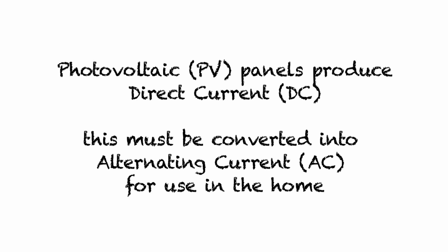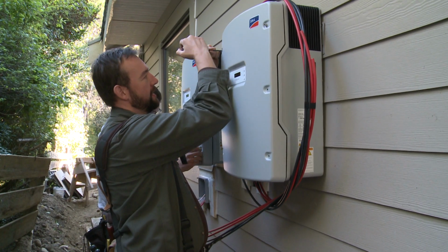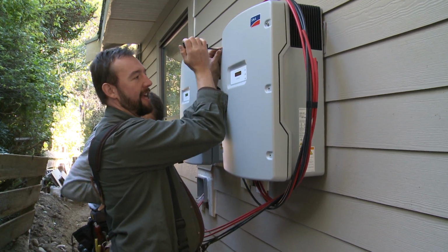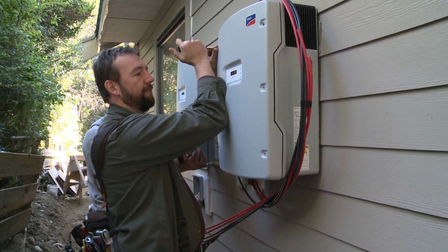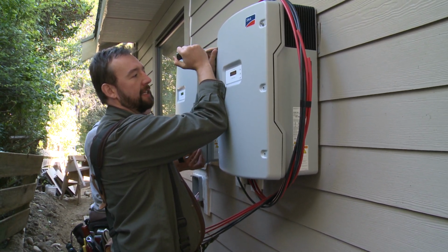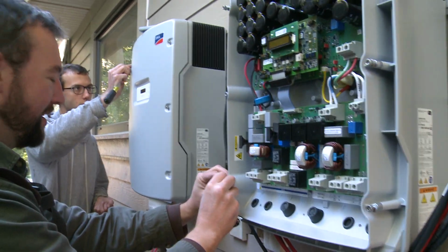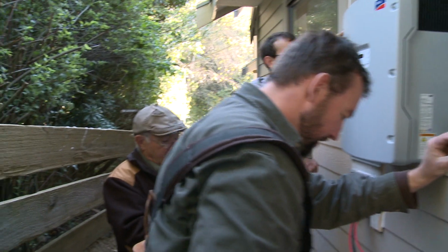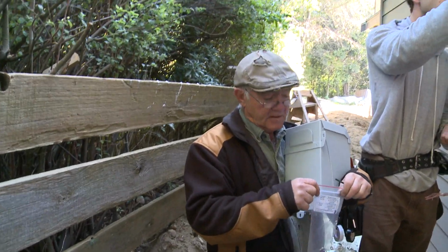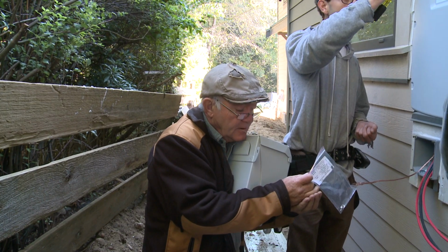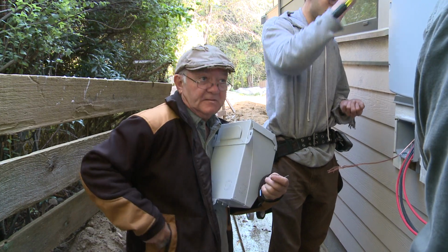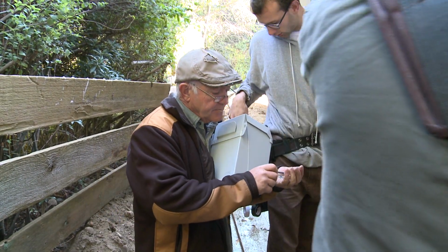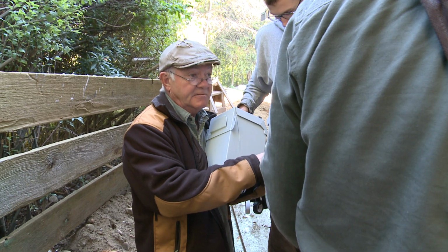These have a lot of great features. Probably one of the most important in terms of safety aspect is something called an anti-islanding feature. So that means when the grid power turns off, these things automatically stop. These things are designed with so many fail-safes that if anything faults at all, they immediately just shut down. So that includes if there's a power outage, the grid fails, these shut down. If there's a failure in the unit itself, it shuts down.